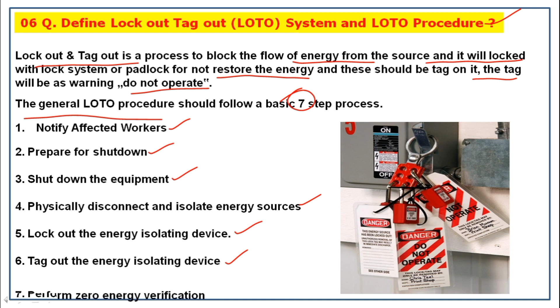Friends, the specific actions for applying LOTO will be different from equipment to equipment and from facility to facility. The general LOTO procedure should follow a basic 7-step process. First one is notify affected workers, prepare for shutdown, shut down the equipment, physically disconnect and isolate energy source, lock out the energy isolation device, tag out the energy isolating device, perform zero energy verification.